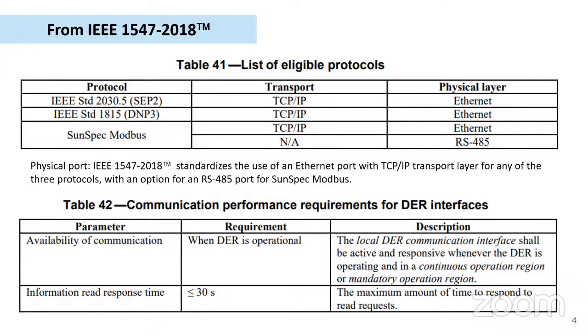So it's not necessary for the DER itself to provide the exact protocol that might get used on the utility or other provider's system. In that case, there is a translator that aggregates and communicates to the utility. And it could be just for a single inverter, or it could be for an entire plant, say.